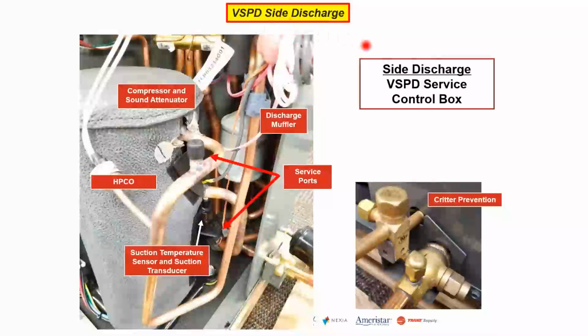Again, we're in the variable speed side discharge control box. They put the critter prevention on there. The earlier models, we had a lot of critter issues. We have our service ports down here. Again, some of them I've seen that pipe that's pretty close right there. Just finesse it out of your way. I apologize for that, but yeah, there's some tight ones in there, that's for sure.